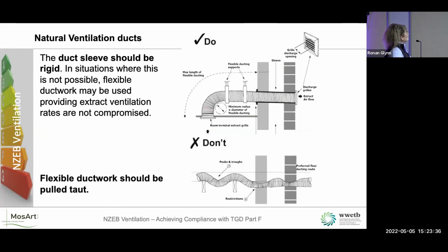The duct sleeves should be rigid, all right? And you often get this from cooker hoods and stuff like that, where they're just shoved out and there's no great care or attention put into them. In situations where this is not possible, flexible ductwork may be used, providing the extract ventilation rates are not compromised. So these have to be checked for validation as well. Flexible ducting should be pulled taut, all right? Otherwise that fan has to work twice as hard to get the air out of there because the duct is all puckered up.